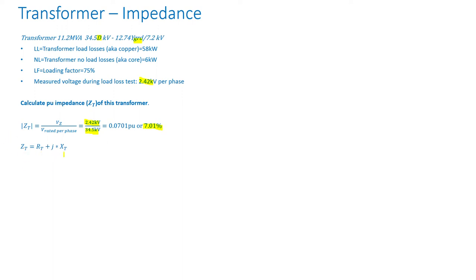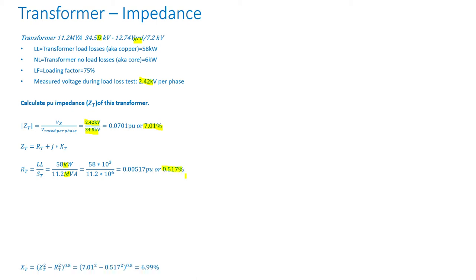The per-unit impedance equals resistance plus J times reactance. The resistance is load loss divided by apparent power: 58 kW divided by 11.2 MVA — be careful with units, since k means times one thousand and M means times one million. This gives 0.517 percent. The reactance is the square root of impedance squared minus resistance squared, which gives 6.99 percent.